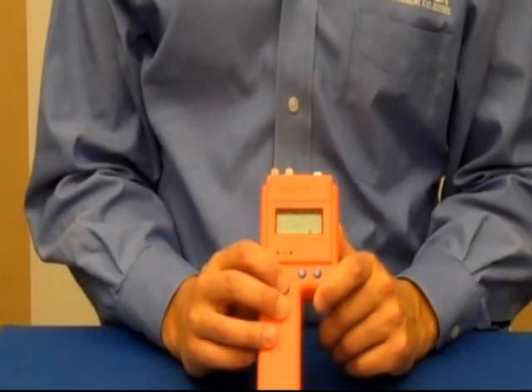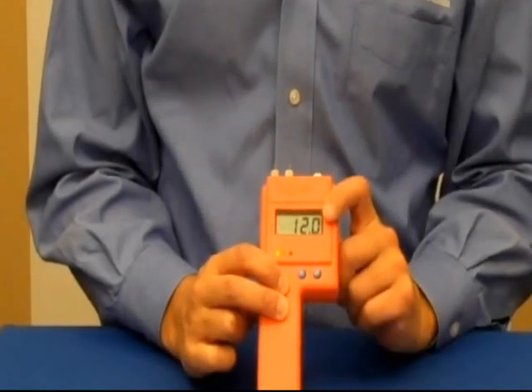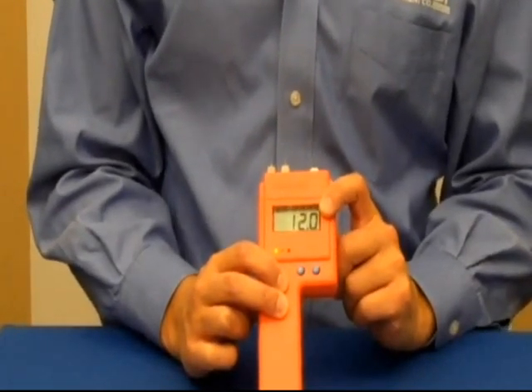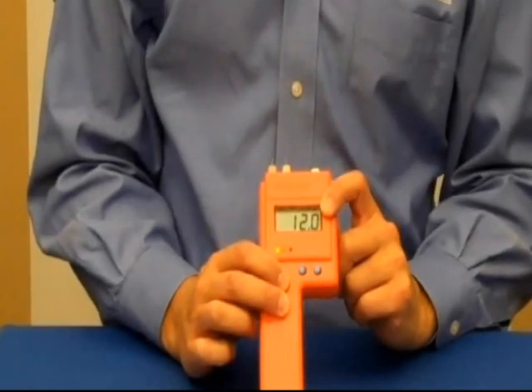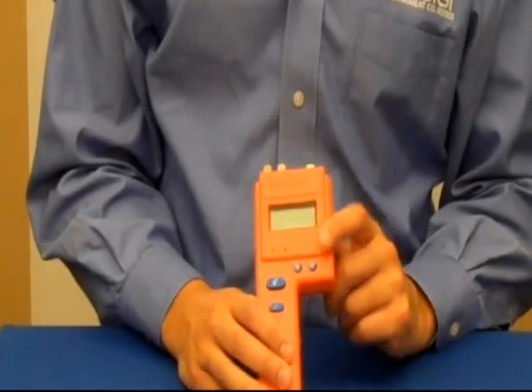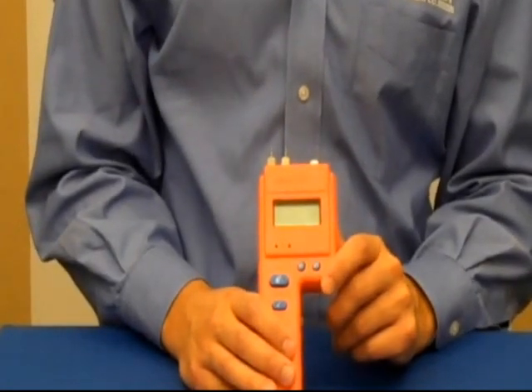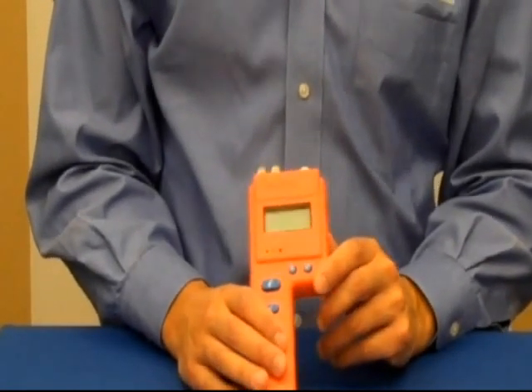The meter also has a built-in calibration check. By just pressing these two buttons, it tells you it reads 12.0 and that's an indication that the meter is in electrical calibration. That's important to do periodically before you take measurements just to make sure that the meter is in calibration.